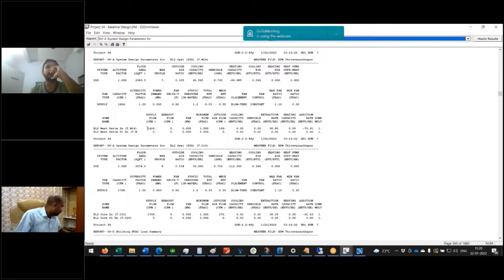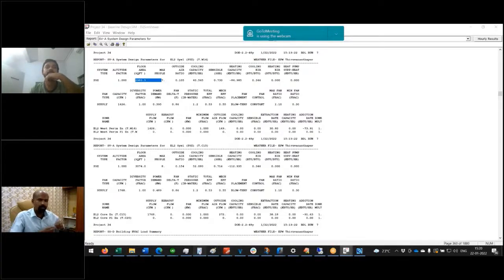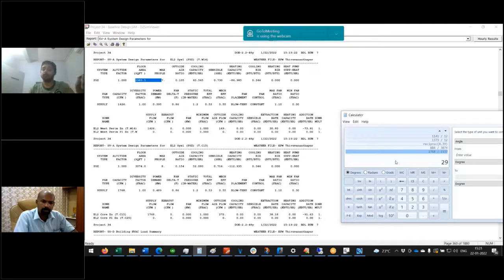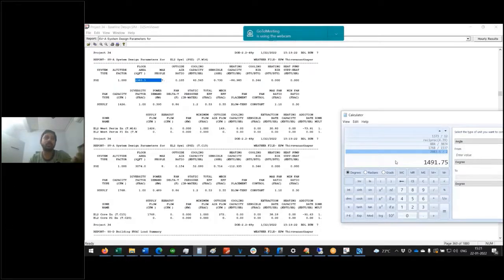So supply CFM is 1426. Floor area will be probably half of this because this includes the plenum zone. So 2983.5 divided by 2 is 1491, and 1426. It's almost giving 1 CFM per square feet. So that's approximately right.